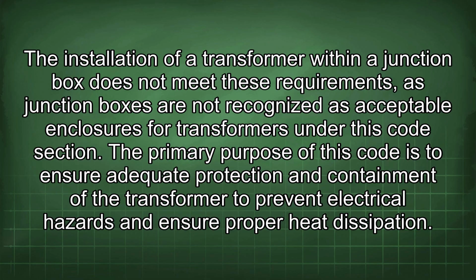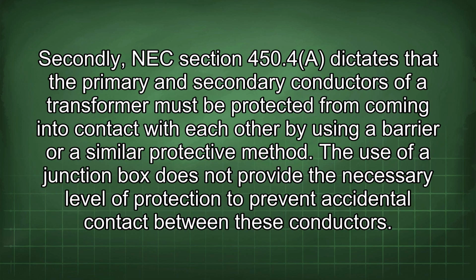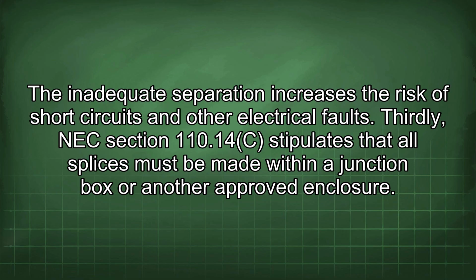The primary purpose of this code is to ensure adequate protection and containment of the transformer to prevent electrical hazards and ensure proper heat dissipation. Secondly, NEC Section 450.4 dictates that the primary and secondary conductors of a transformer must be protected from coming into contact with each other by using a barrier or a similar protective method. The use of a junction box does not provide the necessary level of protection to prevent accidental contact between these conductors. The inadequate separation increases the risk of short circuits and other electrical faults.